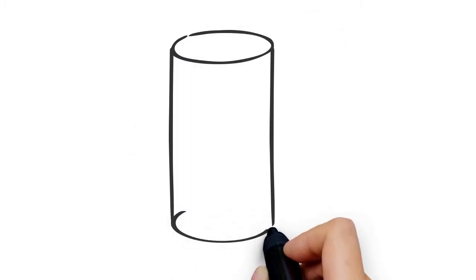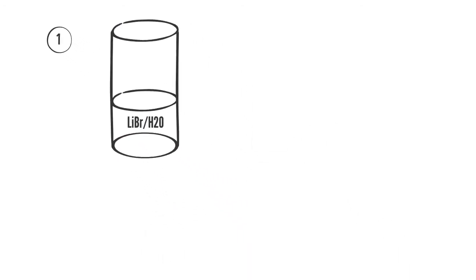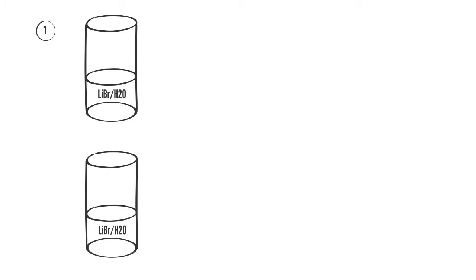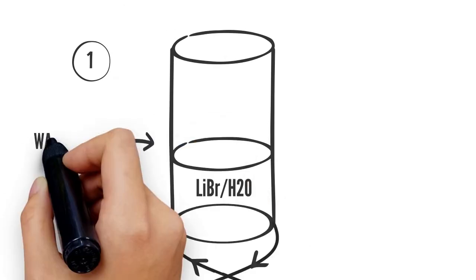A liquid solution of lithium bromide is circulated and diverted between the first and fourth phase chambers of the process system. Lithium bromide acts as an absorbent in the system and has the critical ability that it reacts extremely well with water.